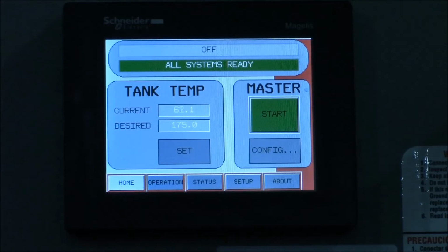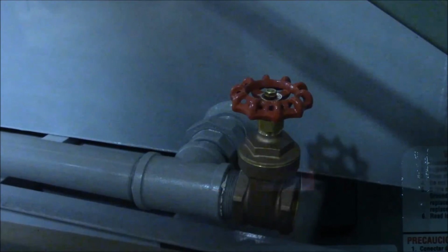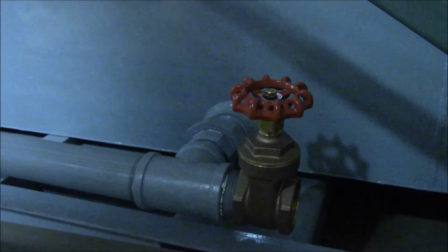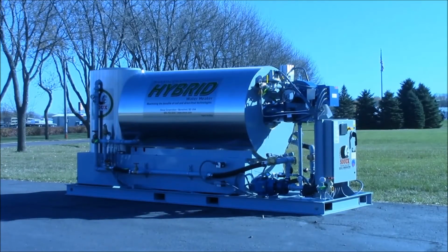If the machine needs to be drained, first shut the inlet and outlet valves, then open the drain valve of the process tank to drain the water left in the heat exchanger. In freezing temperatures, it is highly recommended that you antifreeze the heat exchanger after draining. Consult the Sioux product manual for additional recommendations regarding machine placement, setup connections, operation, shutdown, and freeze protection.